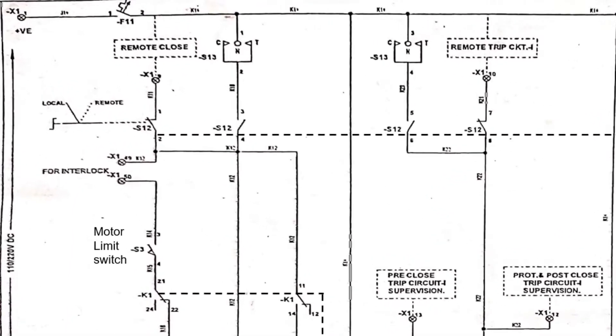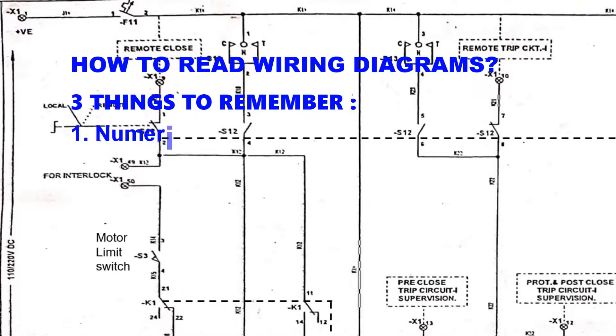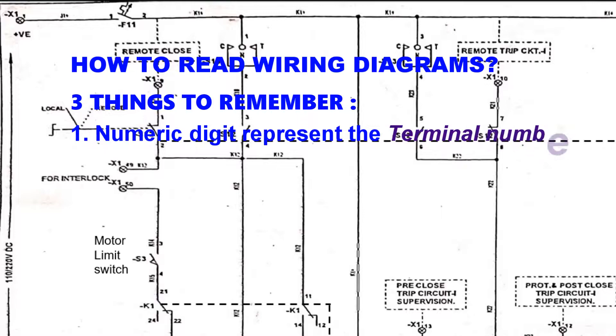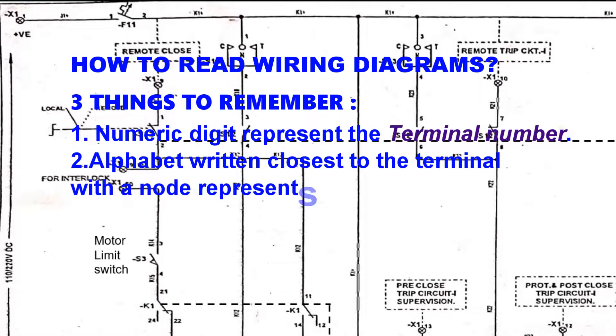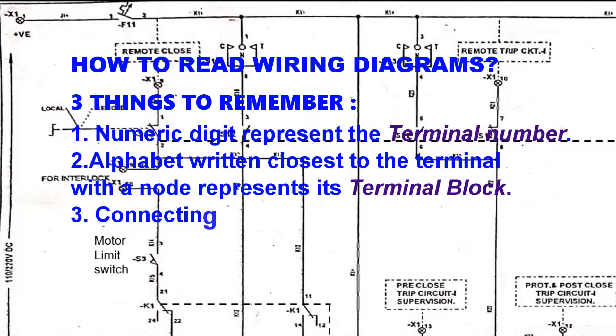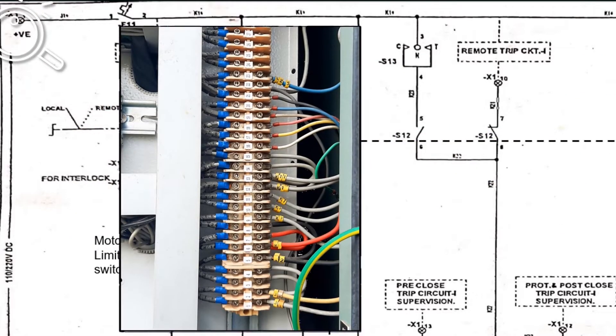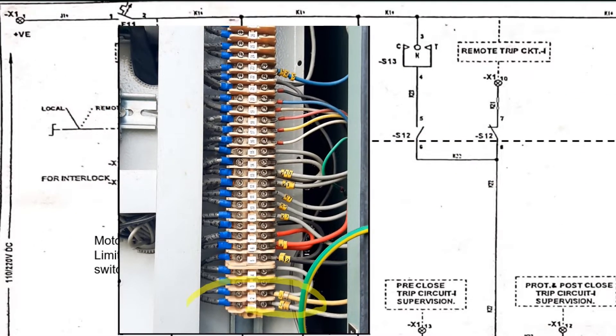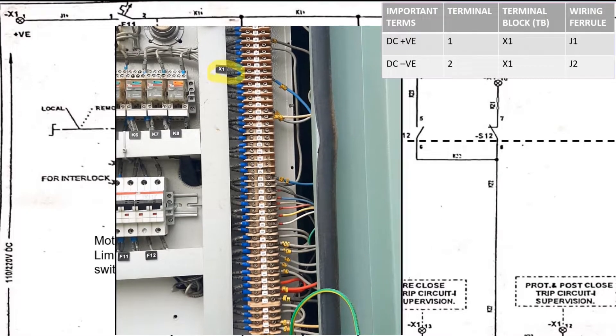Let us start and closely look at the top left of this network diagram. Always remember three things. First, the numeric digit shown always represents the terminal. Second, the alphabet written closest to the numeric digit with a node represents the terminal block. And last, the connecting branch of the network represents the wiring ferrule. From this, we can say that DC positive is given on terminal 1 of the X1 terminal block having a wiring ferrule J1.